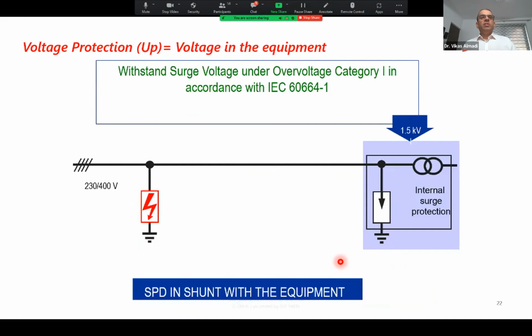So what is the protection criteria for this? This is important to know. How does SPD actually protect? It is not always on. Suppose there is a surge here. The surge will try to go inside the equipment, but by the time, the SPD should come into the picture and divert all the surge. This is how the SPD should work. If it is not there, then all the surge will go here. But if the SPD is there, then of course it will try to divert. Diversion is possible when SPD is in parallel. So the first thing that you get is SPD is in shunt with the equipment. That is the first takeaway from this.